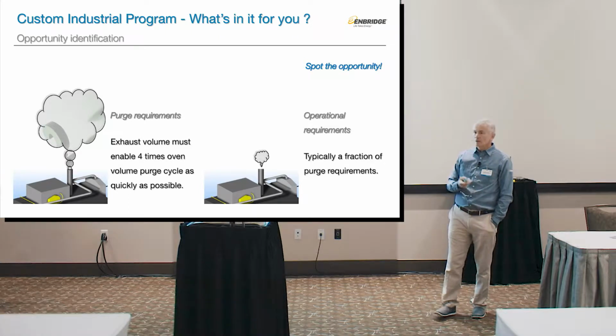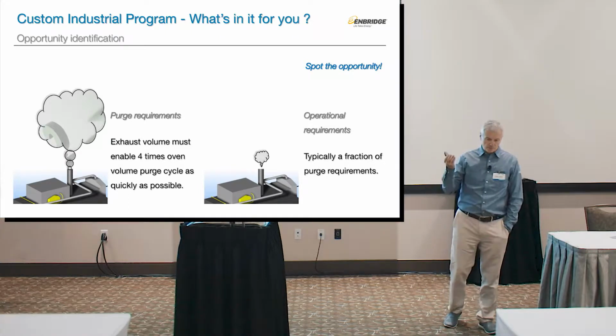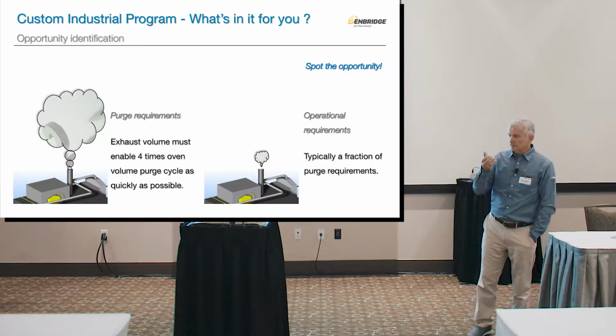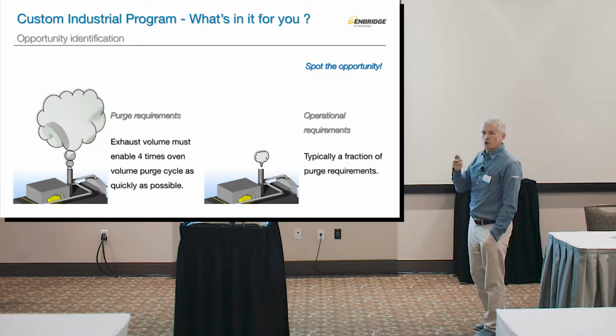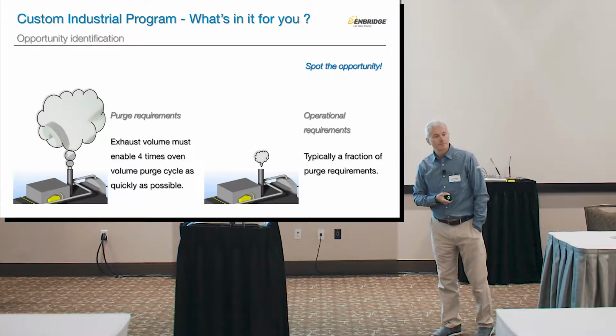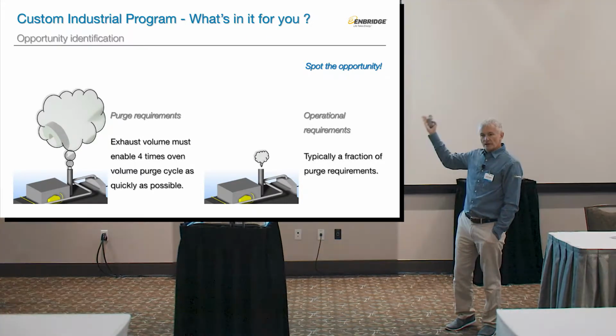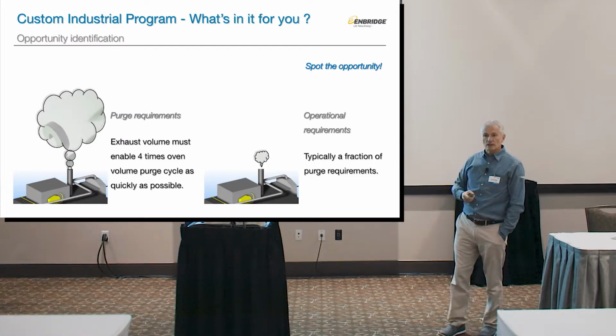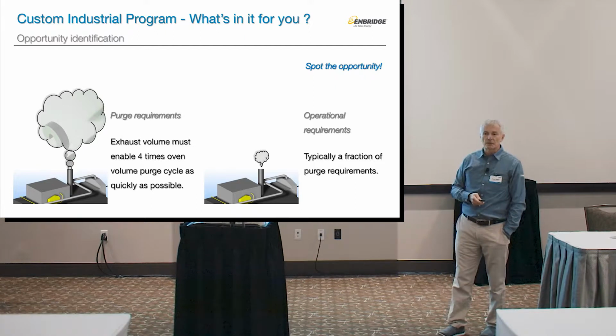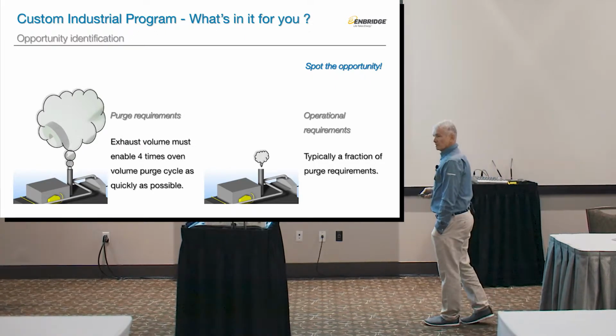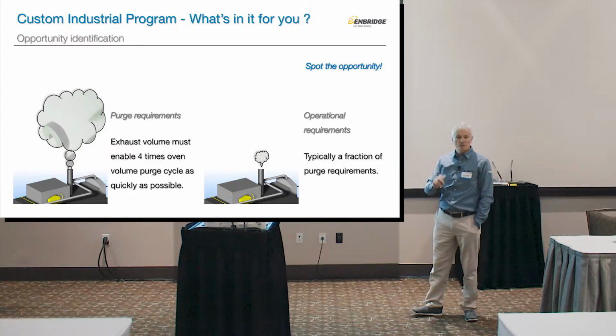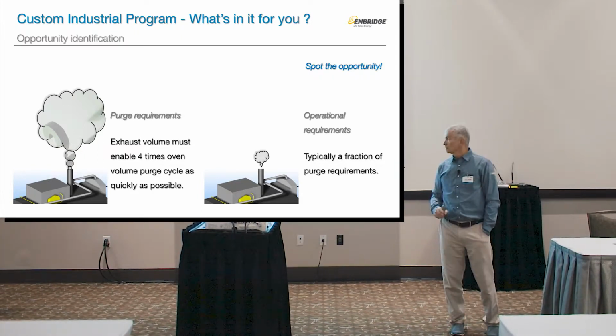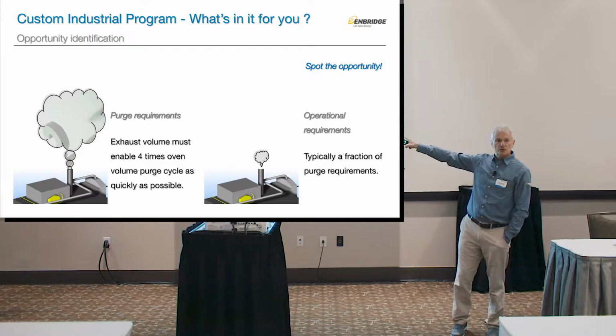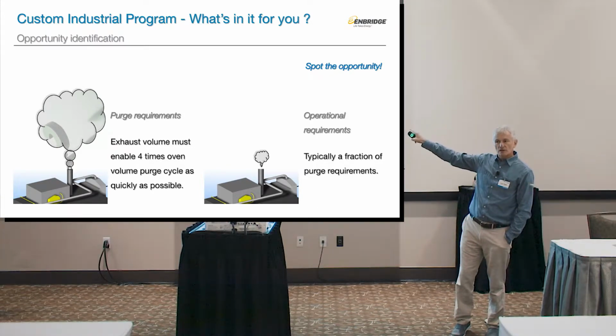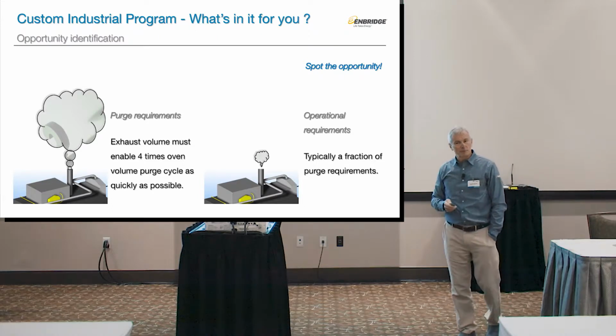So for example, spot the opportunity. We have an oven. Every oven in Ontario under the TSSA has to purge 4 times its volume before it's lit up. So as not to wait 2 hours, we have exhaust volume that enables us to get purged in 15 to 20 minutes maybe. The problem is that the operational requirements for that oven are much, much, much smaller. A fraction. So there is a big discrepancy between what the oven actually puts into the air through the stack and what needs to be put when you're running it at a production level.